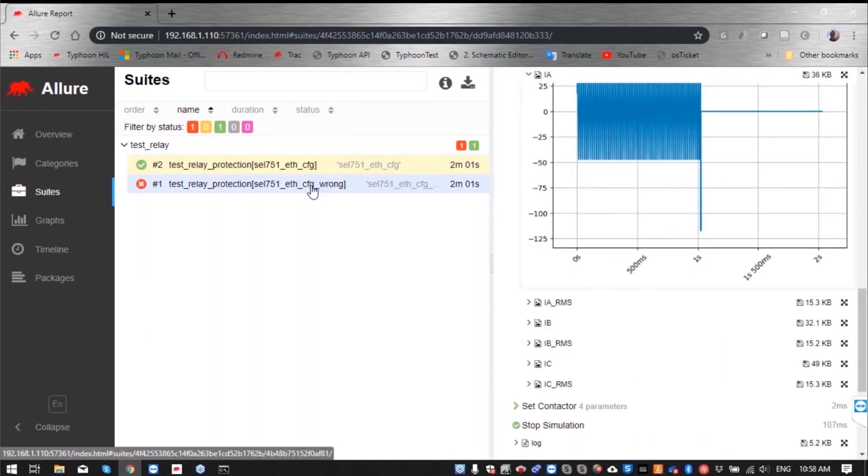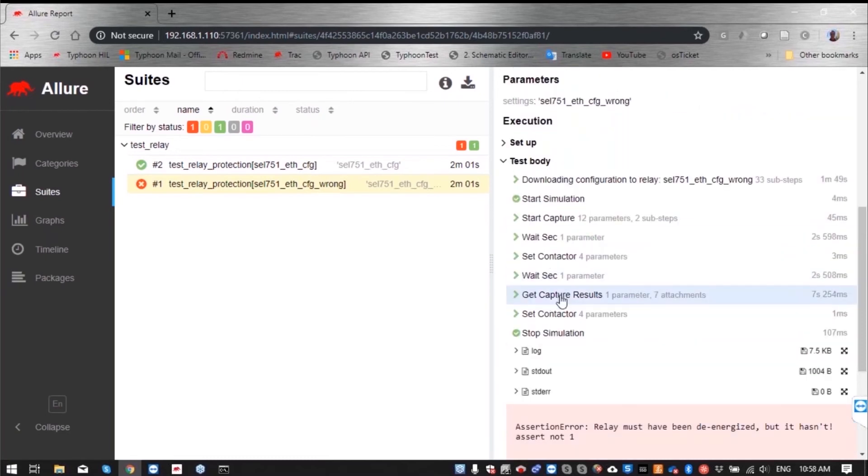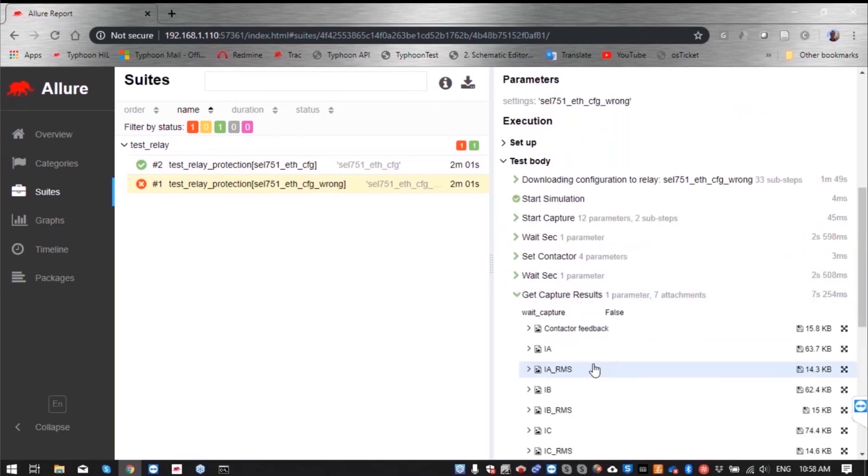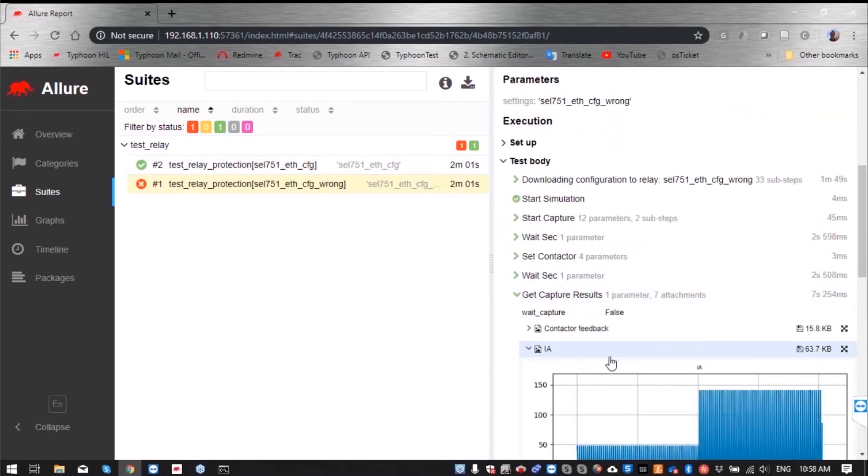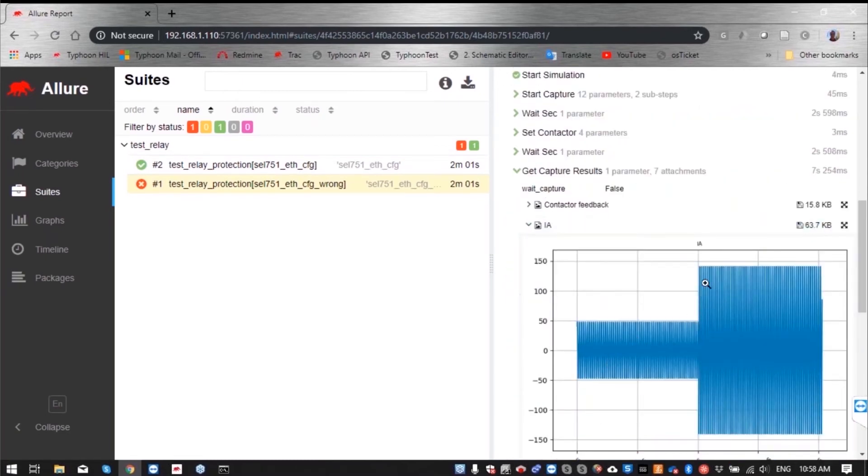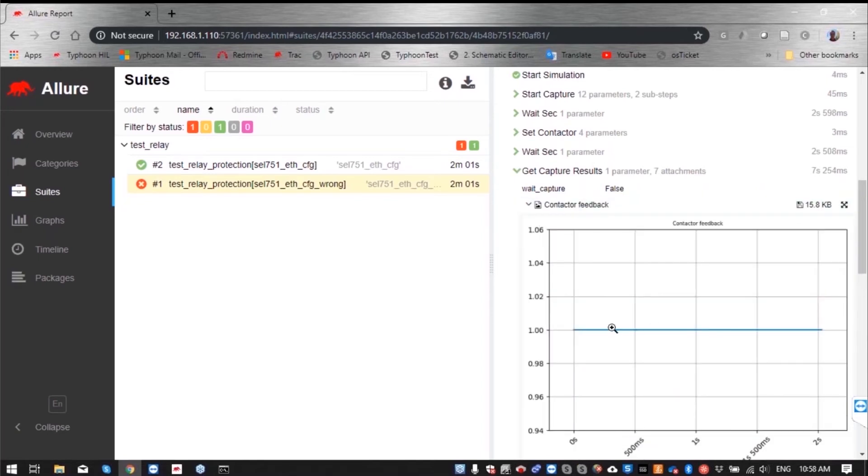However, this other test is not passed. We can see here that current stays at the high level after the short circuit and the contactor feedback signal is still on one. So there were no protection actions on that feeder.